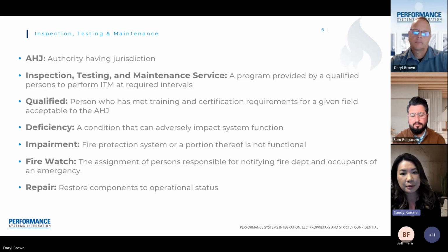A deficiency is when the system has a component that is not functioning properly or is missing a component that does not affect the operation of the system, but is still required by code. An example of that would be missing fire signs that indicate parts of the systems. Now, an impairment is when the system or part of the system is not functional. Different types of impairment would be emergency impairment, like unexpected event water supply interruptions, or fused sprinkler heads. There's also planned impairments, such as pre-planned shutdowns of the system for repairs or modifications. And fire watch. Fire watch is when an individual is responsible for notifying the fire department or the occupants of the site of an emergency. This would happen if the fire alarm system or fire sprinkler system is out of service for long durations of time. And finally, repair is to fix and restore components to operational status.